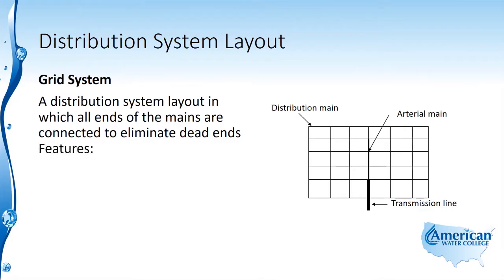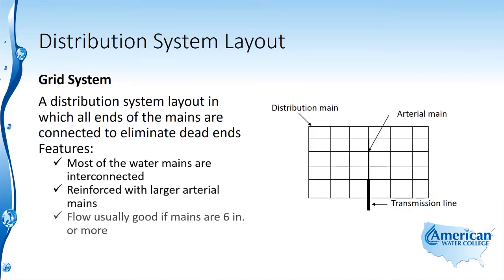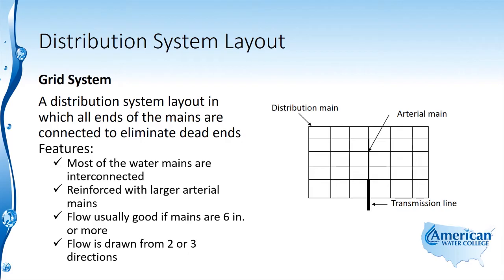Features of the grid system include: most of the water mains are interconnected, the mains are reinforced with larger arterial mains, flow is usually good if the mains are six inches or more, and you'll draw flow from two to three directions.